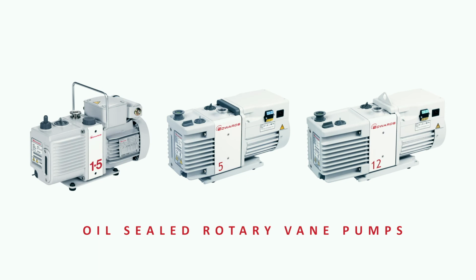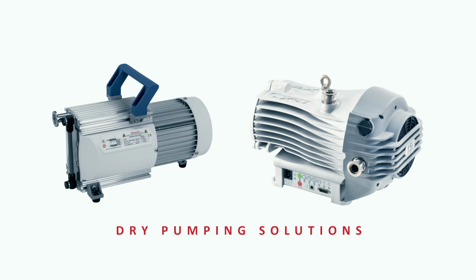Then select your backing pump. This can be either an oil-sealed rotary vane pump, E2M 1.5, RV5 or RV12 plus EMF oil mist filter, or for dry pumping solutions, select from XDD1 diaphragm pump or our NXDS range of scroll pumps. Then you can select a solenoid vent valve if required, and finally identify your electrical supply.